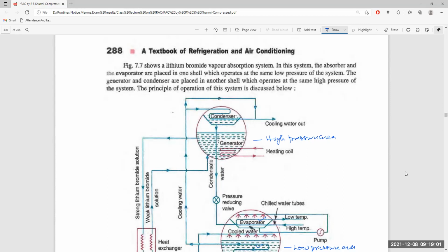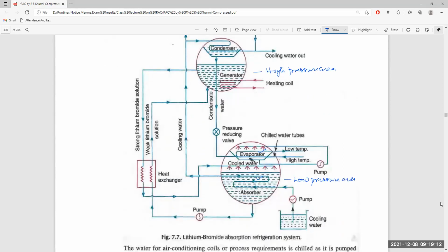Here, one portion of the cooling water is going around the condenser, so this is water cooled here. This cooling water is pumped from the cooling water pond, which is coming from here. Cooling water pumped from here goes through here and goes first to the absorber, then to the condenser, where it takes away the heat of condensation and dilution. Then the condensate from the condenser is supplied to the evaporator to compensate.